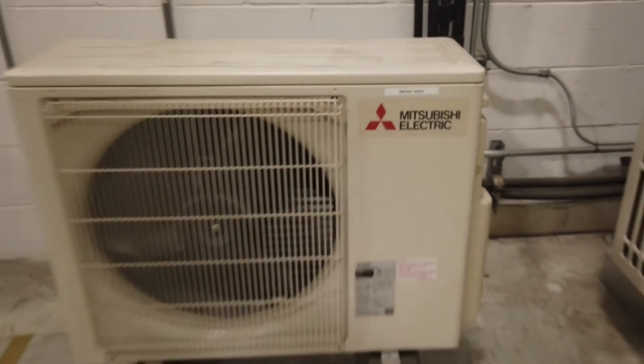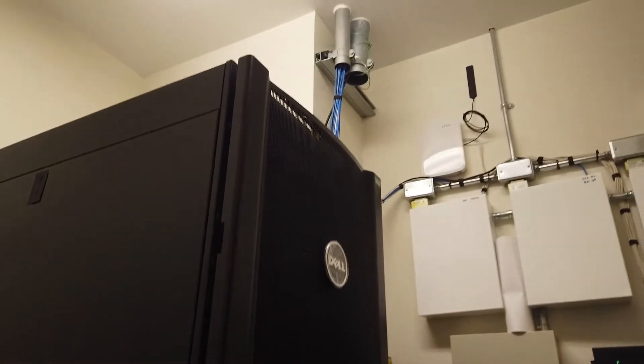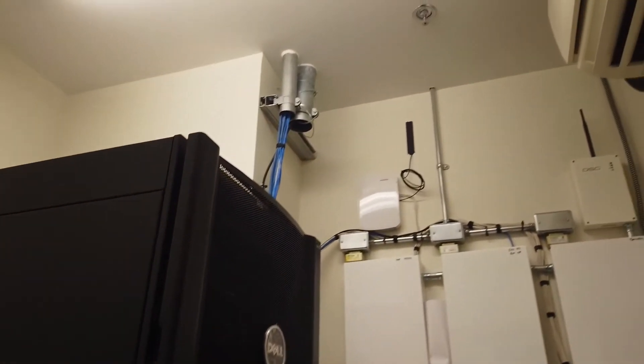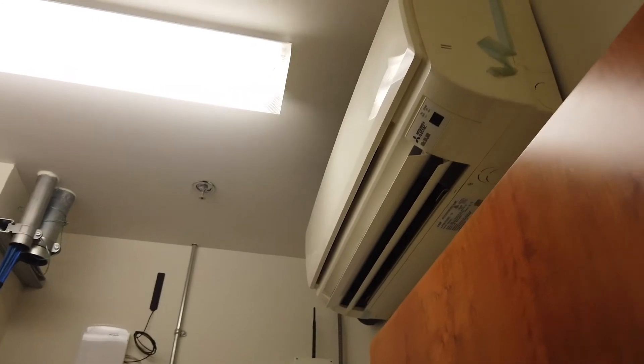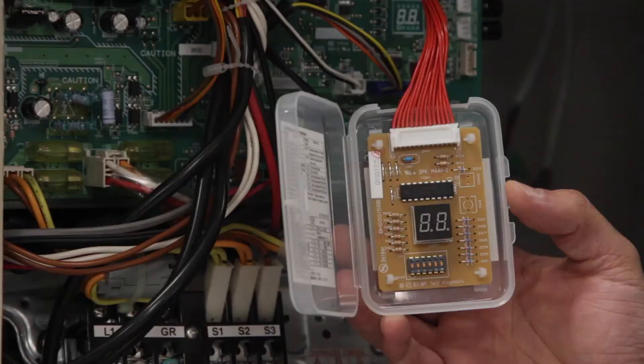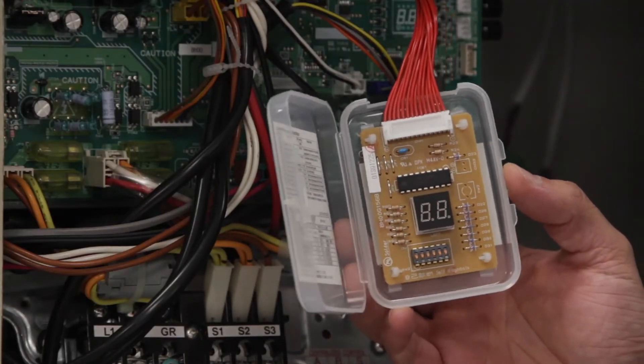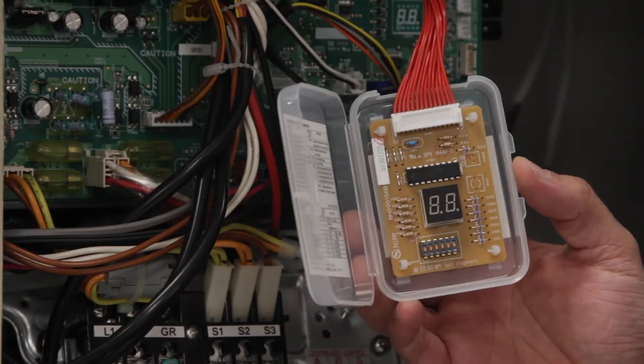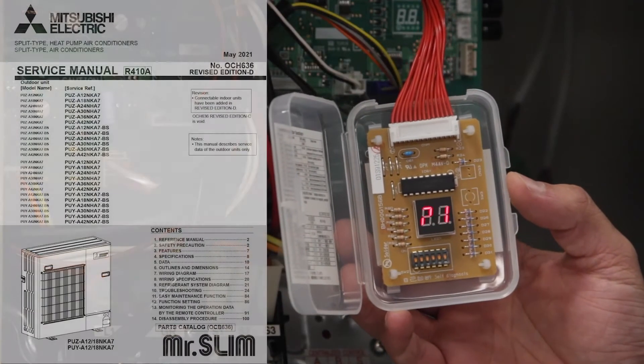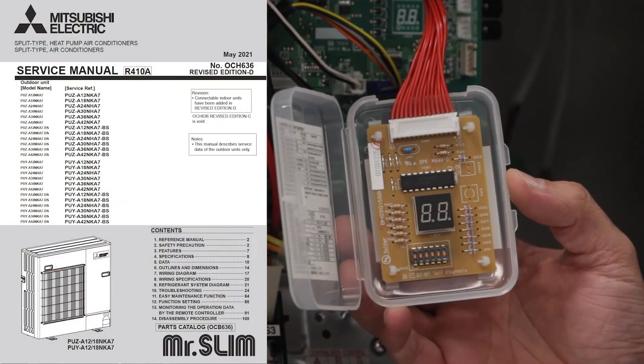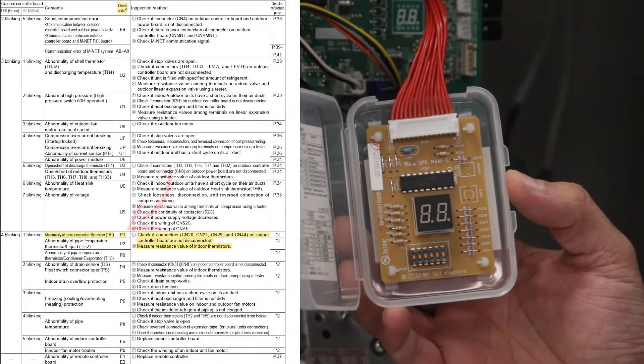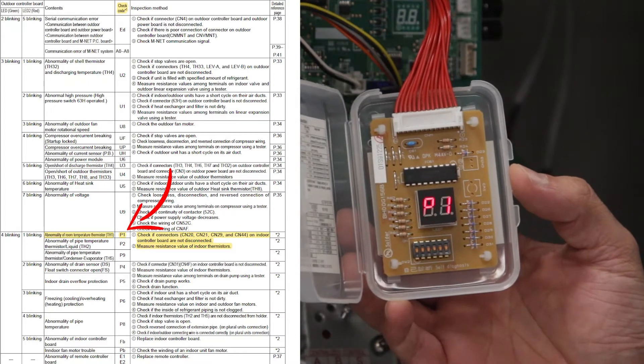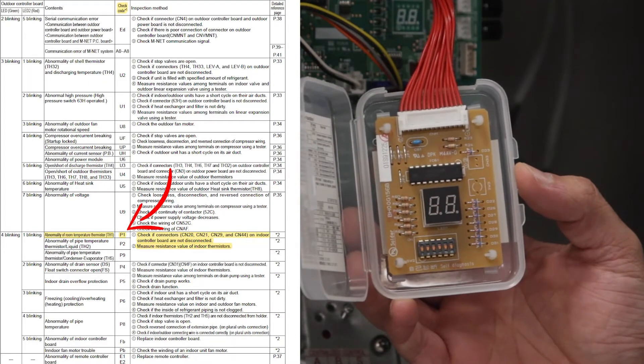For this service call, we have a P-series outdoor unit inside a warehouse, with the indoor unit located in a server room. The indoor unit's accessibility is limited, but I was able to identify a P1 error via the service tool. Upon referencing the flash code to the service manual, the error code indicates an intake sensor error of room temperature TH1 thermistor.